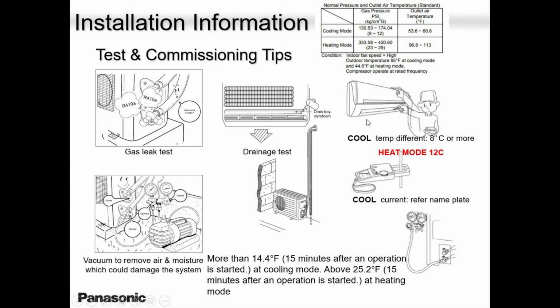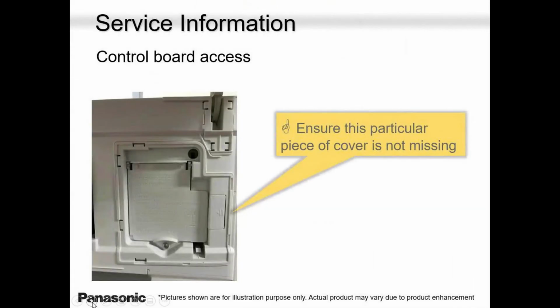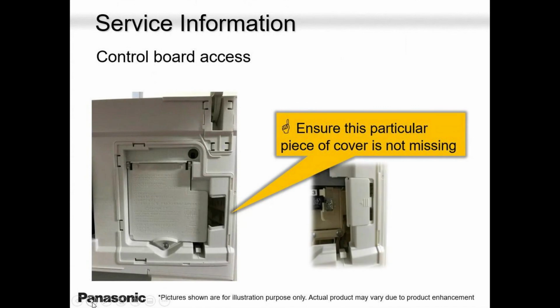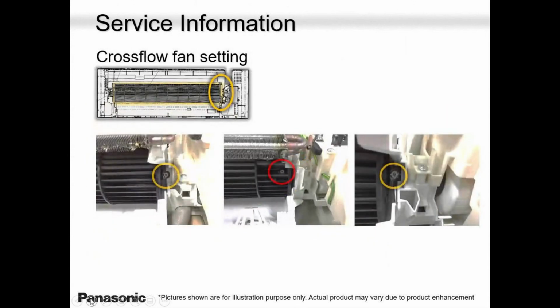And this is your outlet air temperature out of your indoor unit. In cooling, it should be around 50, 53, up to 60. In heating, anywhere from 96 to 115. And if you're getting more than 115, let's say 120, that means your fan is not blowing hard. There is a problem. Maybe the sensor. Okay? So please keep these details always in the back of your mind.